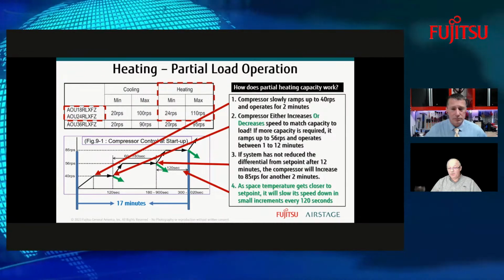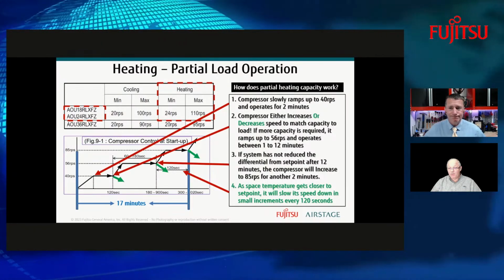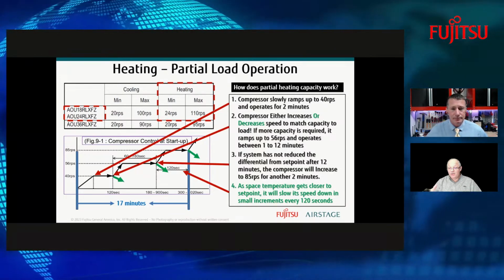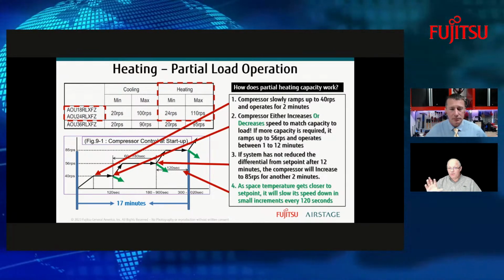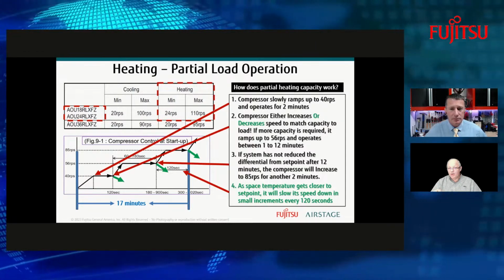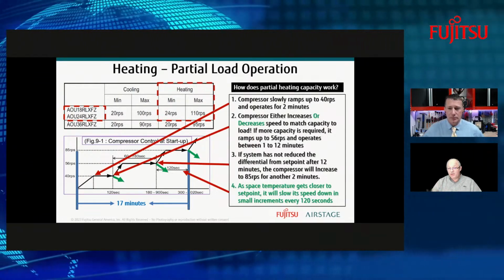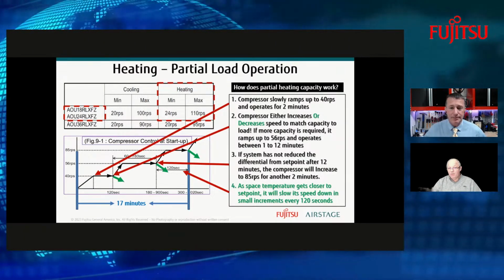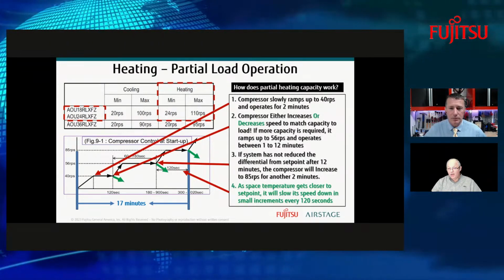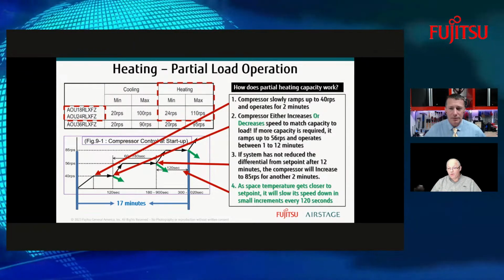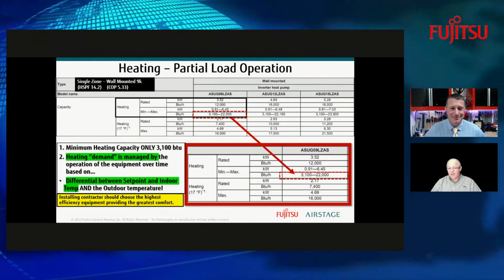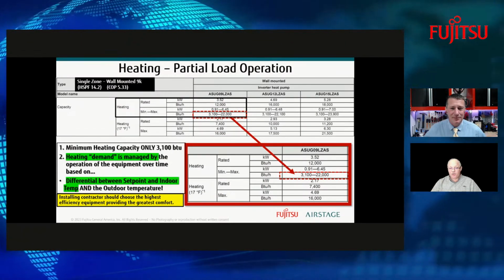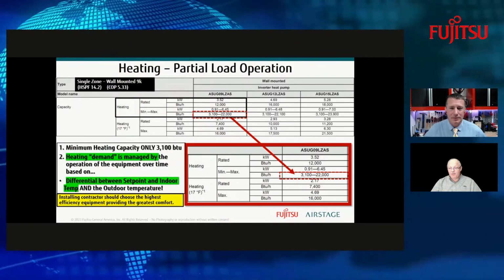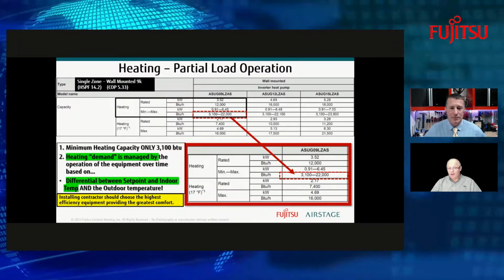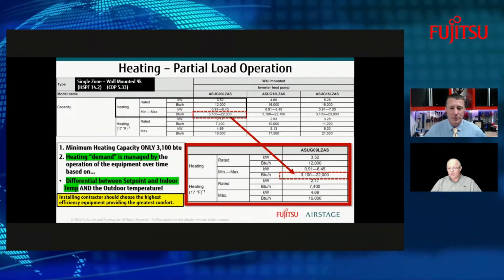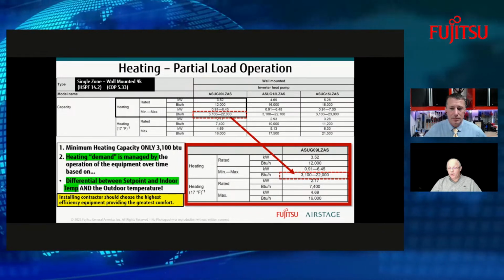If it does, it's going to move up to the next RPS that's programmed to run at. And so you see that there's a thought process from engineering on how we're going to run this for a certain length of time. This will vary from manufacturer to manufacturer. Yeah, absolutely. But everybody's doing something similar, and at what point they're going to decide they're going to ramp to a certain speed. Right. And so when we're talking about partial load, you can see from this example that this little 9,000 indoor wall mount unit has a heating range of between 3,100 to 22,000.